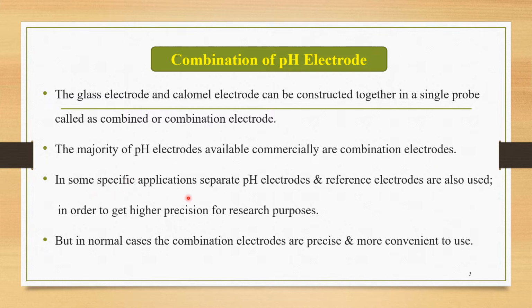In specific applications, separate pH electrodes and reference electrodes are also used in order to get higher precision for research purposes. Even though these combination electrodes are commonly used commercially, in some research work the separate electrodes, that is the reference and calomel electrodes, are used for higher precision. But in normal cases, the combination electrodes are precise and more convenient to use, and that's why they are commonly used nowadays for pH measurement.